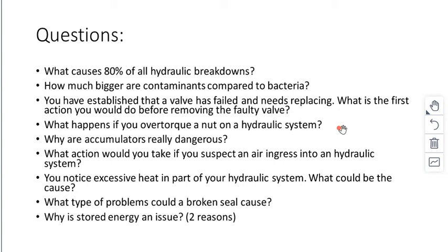Next question. You have established that a valve has failed and needs replacing. What is the first action you would do before removing the faulty valve? I'm going to give you a moment. You should depressurize the system. That should be the first action. And then make sure that it actually is depressurized and that there's no residual pressure by operating valves and opening them up whilst the pump is not working to allow the oil to drain back to tank.